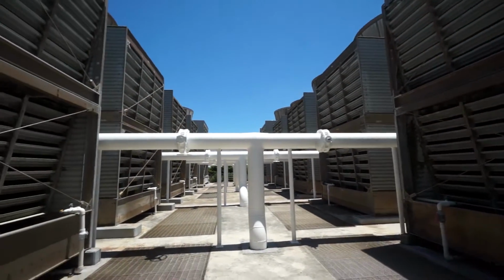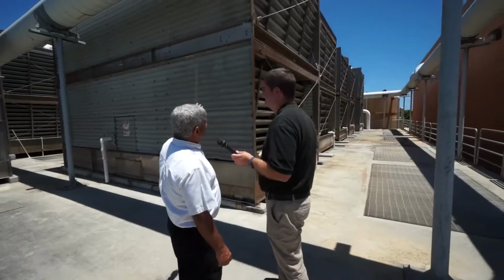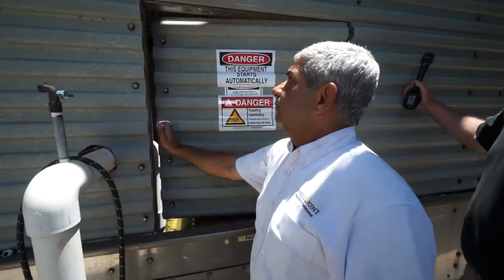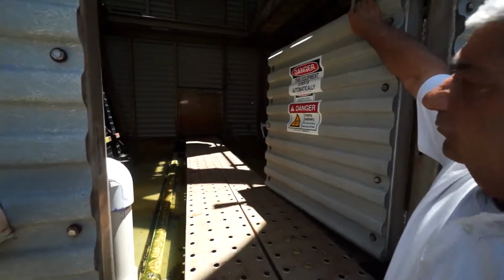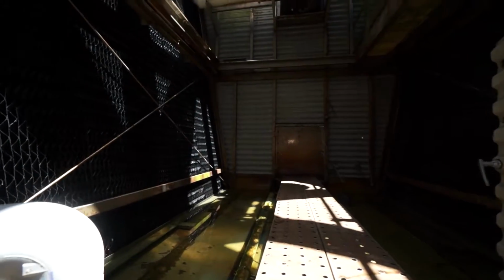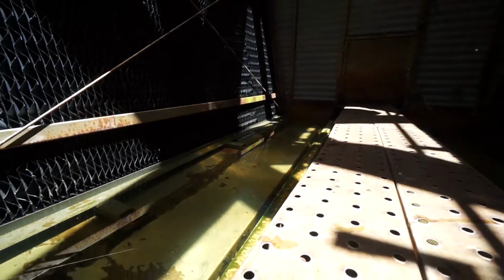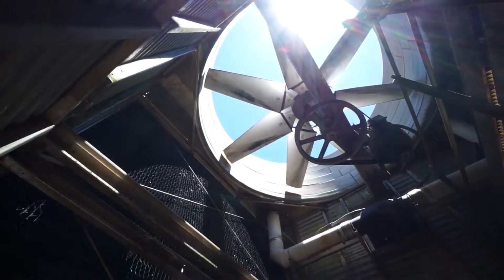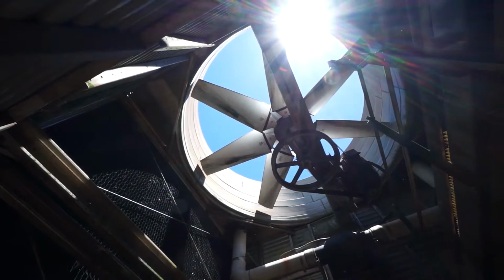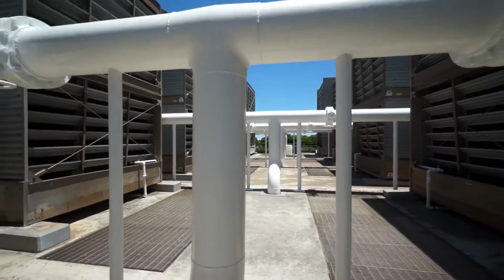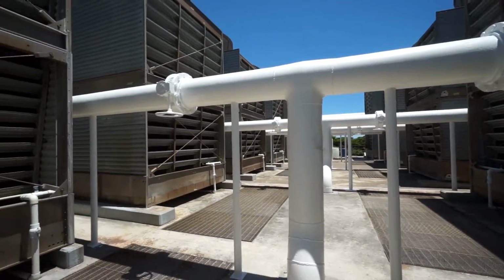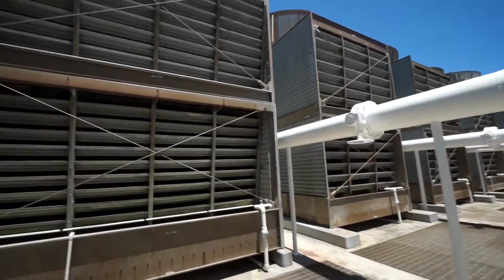So how many of these are here? Okay, I'm going to call it a cell. This first cell is 600 tons. There are 2 of them per chiller because the chiller is 1,200 tons. We did it with 2 cells on purpose because during the winter you may not have to run both towers to cool this machine, but in the summer it takes 2 of them to cool one machine.